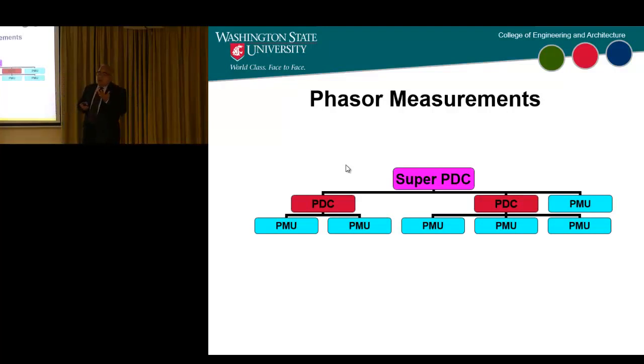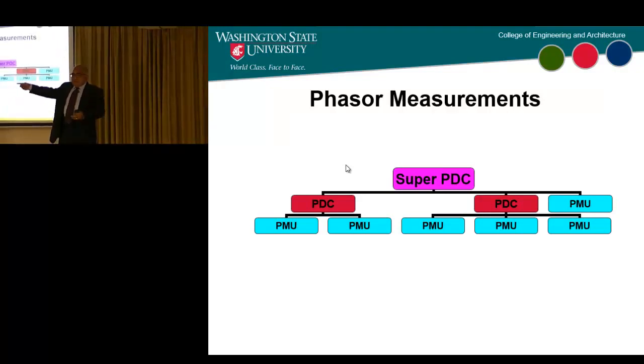Now with this you can, but one of the problems depends on how you move this PMU data. Right now it's being moved hierarchically from the substation to the control center, and from the control center onward. For example, you may want to know the phase angle difference between somewhere in Germany and Paris. Remember, something in Germany took out Paris a few years ago—Paris was blacked out because of a problem in Germany. So the only way you can look at that angle difference is if the PMU data was moved up to a point where these two angles can be compared.